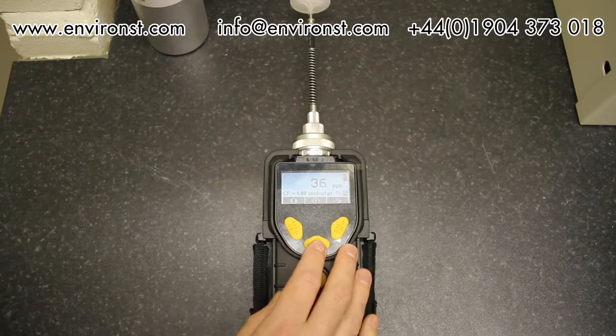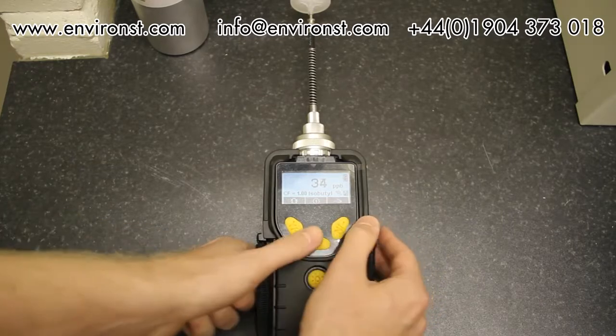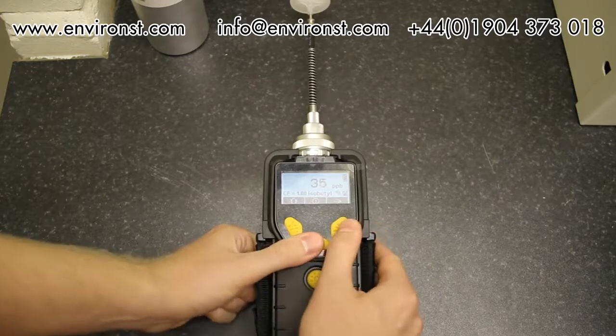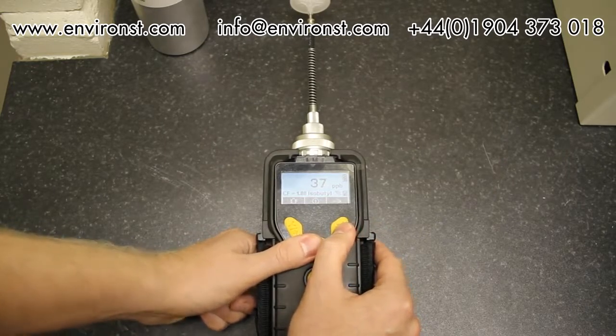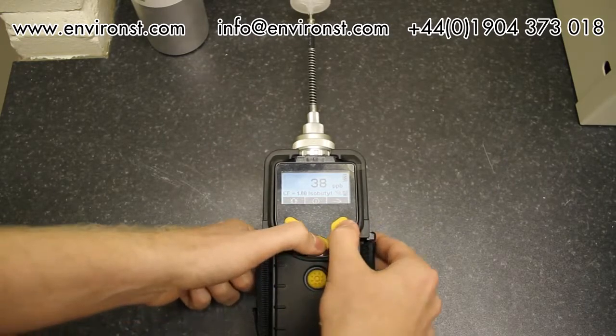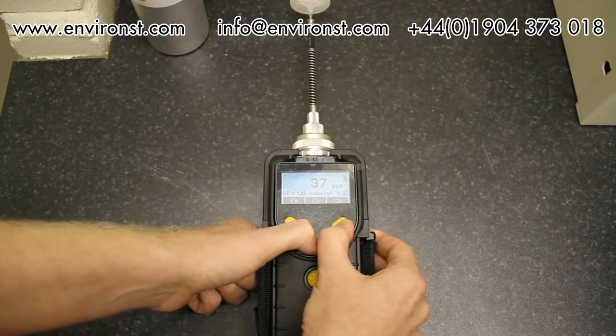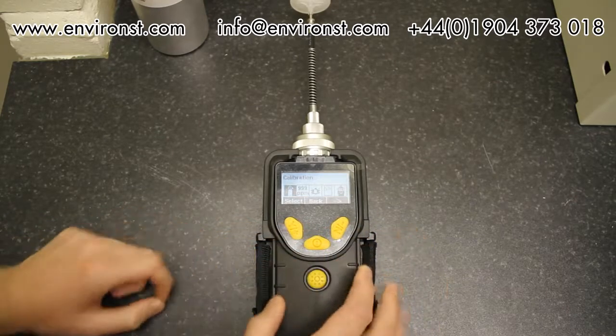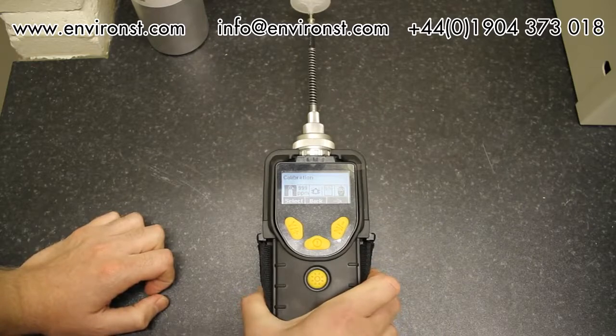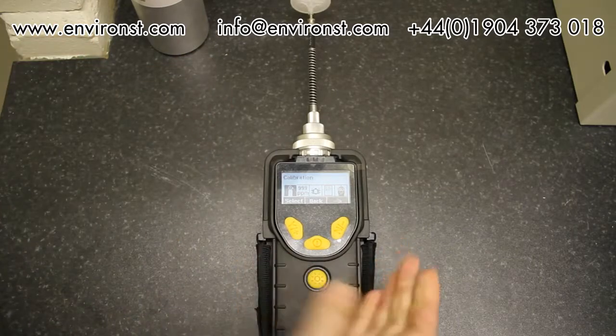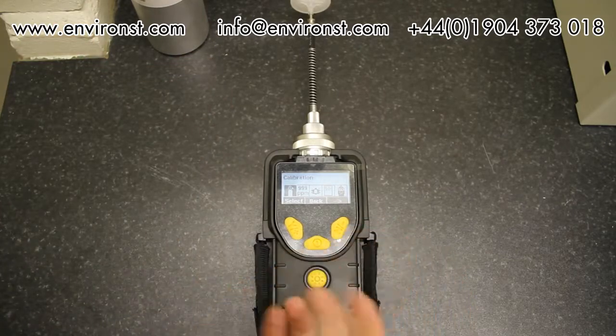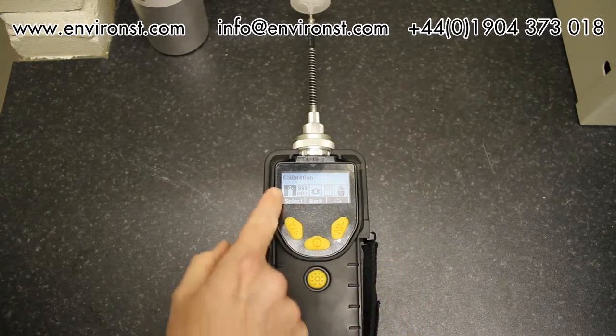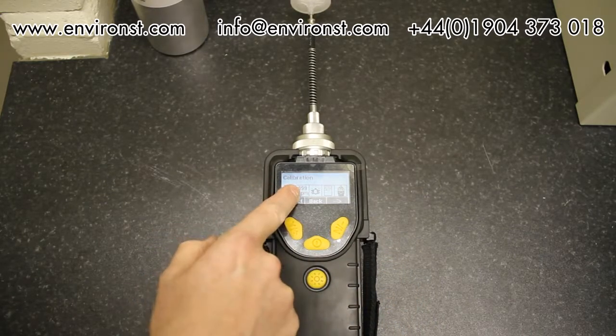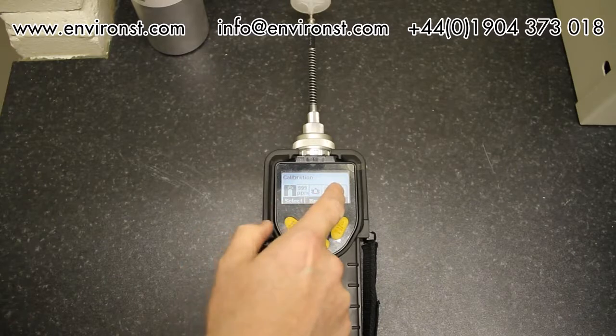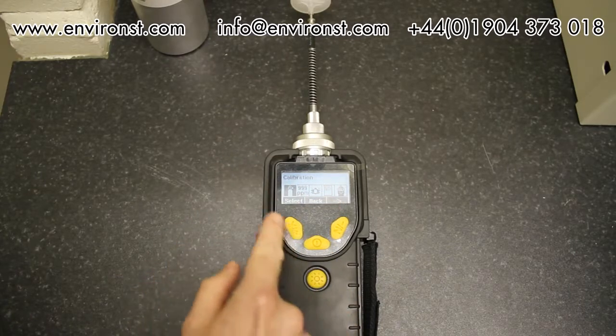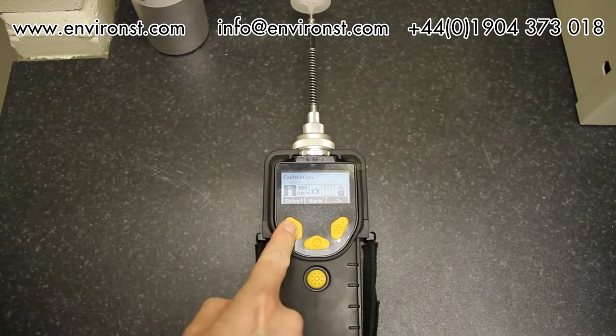So what we're going to do now is I'm going to show you quickly how to calibrate the instrument, as this is subtly different to all other RAE Systems PIDs. So if we press power and no at the same time and hold for 5 seconds. Sometimes it will ask you for a password. If it's the first time that you've been running this unit, it will ask for a password, and it's normally 4 zeros. So we've got our calibration menu, measurements menu, alarms, data logs, and general monitor setup. So we're going to quickly go into the calibration menu.